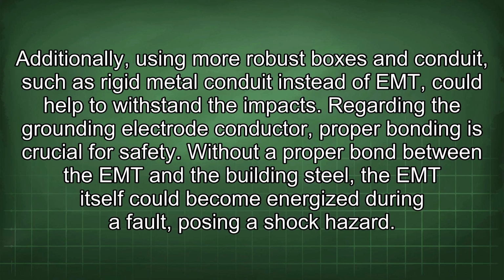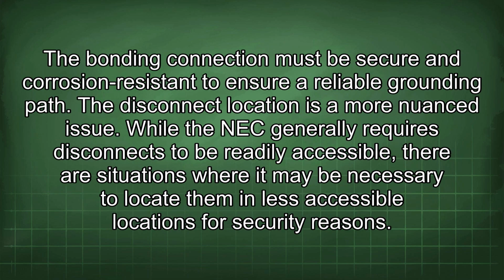Additionally, using more robust boxes and conduit, such as rigid metal conduit instead of EMT, could help to withstand the impact. Regarding the grounding electrode conductor, proper bonding is crucial for safety. Without a proper bond between the EMT and the building steel, the EMT itself could become energized during a fault, posing a shock hazard. The bonding connection must be secure and corrosion resistant to ensure a reliable grounding path.